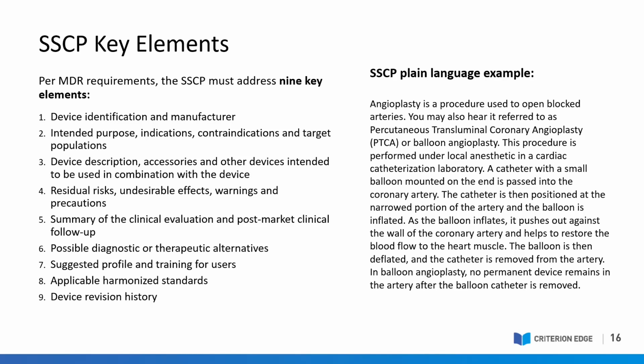Device description, accessories, other devices intended to be used in combination with the device. What are the residual risks, undesirable effects, warnings, and precautions? The summary of the clinical evaluation activities, and the post-market clinical follow-up. That's a summary of the data.